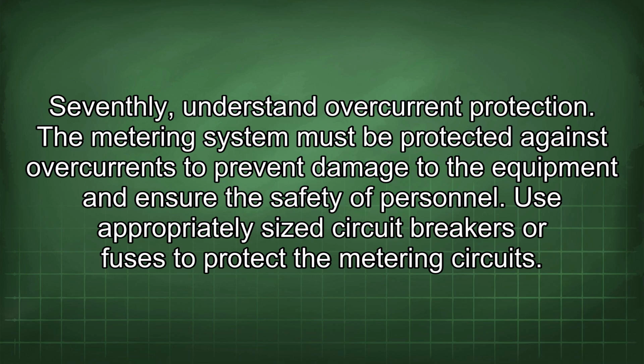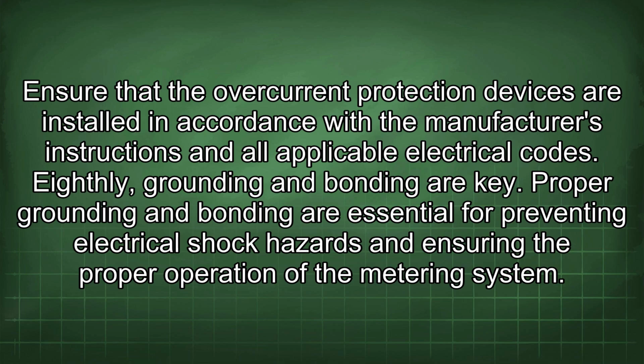Seventhly, understand overcurrent protection. The metering system must be protected against overcurrents to prevent damage to the equipment and ensure the safety of personnel. Use appropriately sized circuit breakers or fuses to protect the metering circuits. Ensure that the overcurrent protection devices are installed in accordance with the manufacturer's instructions and all applicable electrical codes.